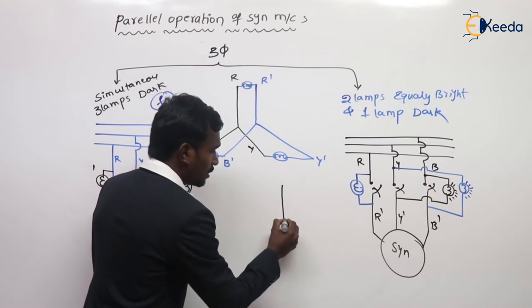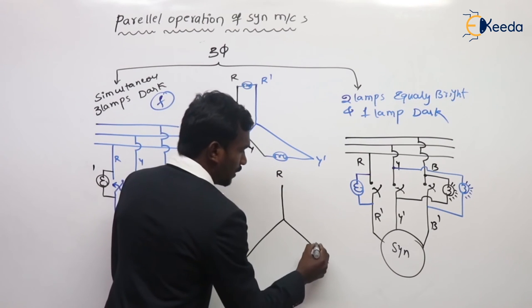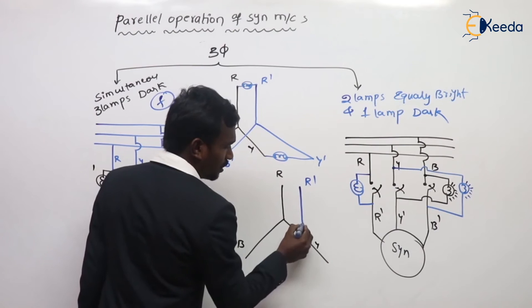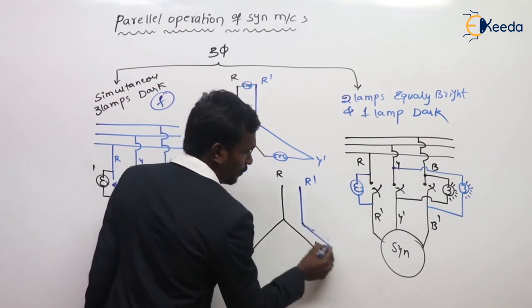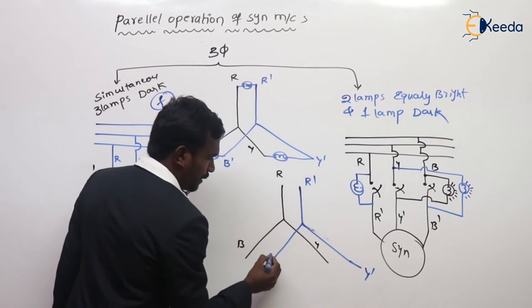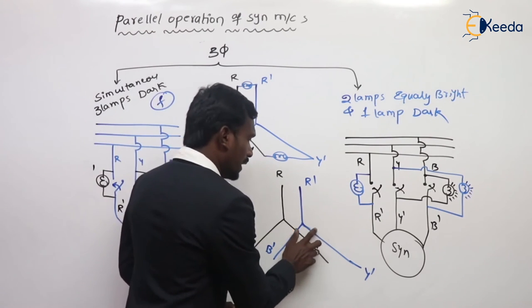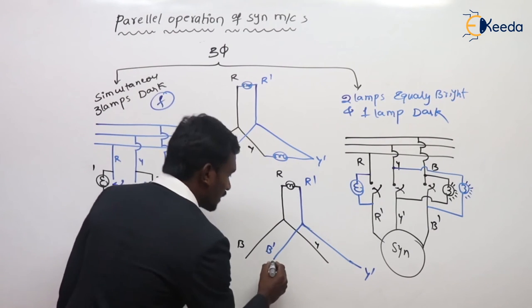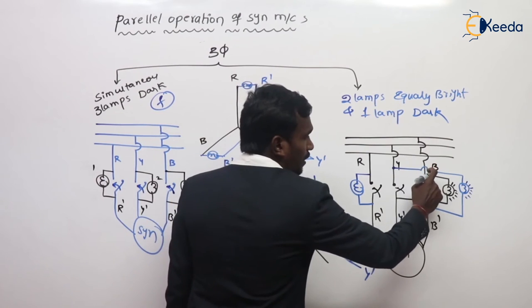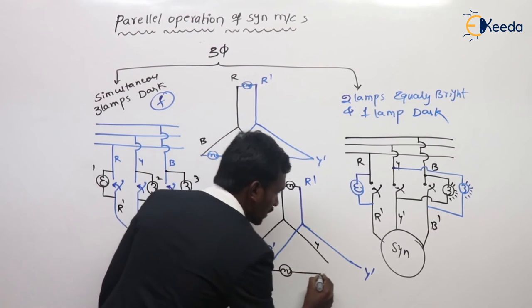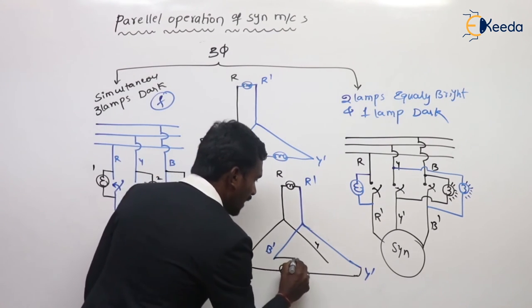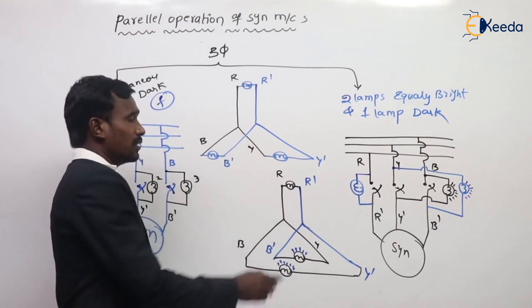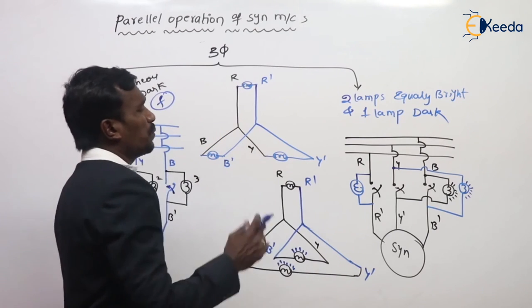To summarize the vector connections: first lamp is connected between R and R', which gives dark. Next lamp is connected between B and Y', and the third lamp between Y and B'. These two cross-connected lamps give bright light, while the R-R' lamp gives dark. Like that, we can make the machine parallel. This is the synchronization method for three-phase systems.